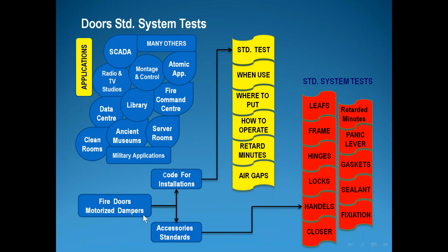So we have the fire doors and the motorized damper. We have a code of installation. There are special proper ways for the installation of these two items and the accessory standards. I mean the hinges, the lock, the frame, the sealant of the frame, or the handle. All these are stated in many standards. There is a European standard and there is an American standard for these testing types, to be sure that this will seal the smoke and the fire.